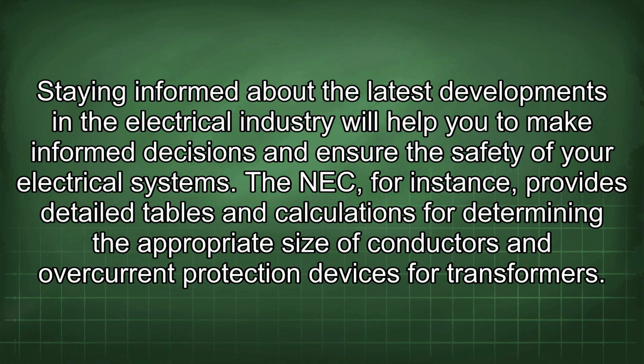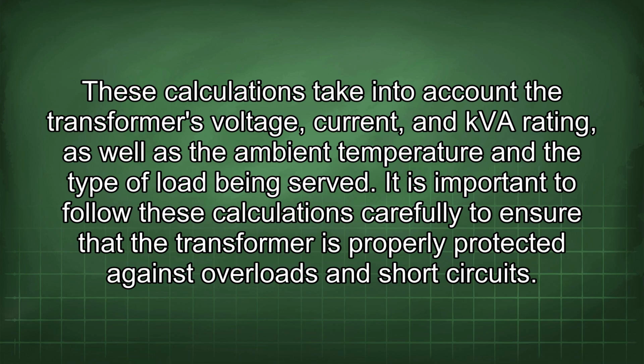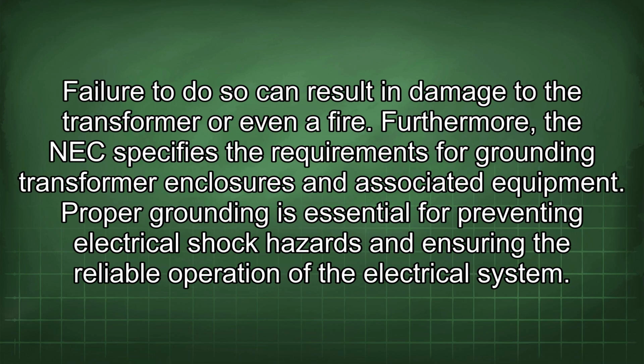The NEC, for instance, provides detailed tables and calculations for determining the appropriate size of conductors and overcurrent protection devices for transformers. These calculations take into account the transformer's voltage, current, and kVA rating, as well as the ambient temperature and the type of load being served. It is important to follow these calculations carefully to ensure that the transformer is properly protected against overloads and short circuits. Failure to do so can result in damage to the transformer or even a fire.